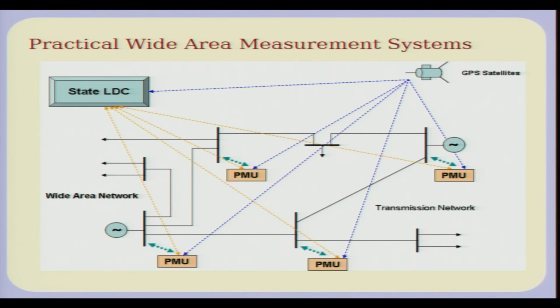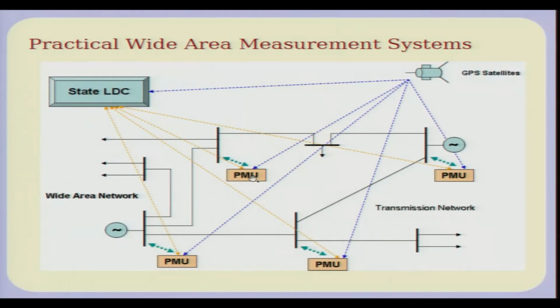Now, a practical or commercial wide area measurement system would use GPS satellites, the global positioning system, the same thing used to pinpoint your location on your mobile phone, to give a much better synchronization signal. The synchronization error with GPS based time synchronization is much smaller, of the order of a few microseconds or less. The PMUs, phasor measurement units, measure not only frequency but actually sample the voltages and compute the phasor.